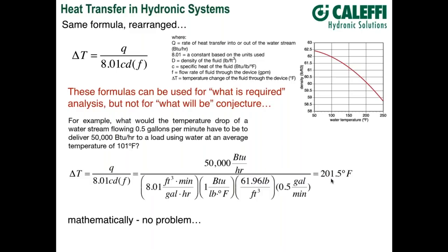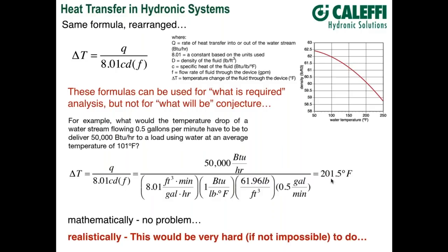To track total energy moved over a period of a month, conditions change — flow and delta T vary. In exact terms this requires integration over time, but practically we take snapshots, perhaps every 10 seconds, look at delta T and flow rate, assume they're constant for that interval, calculate heat moved, then accumulate incremental totals. Adding them all together gives a close approximation of the exact calculus result. We'll be talking more about BTU metering in the next issue of Hydronics.